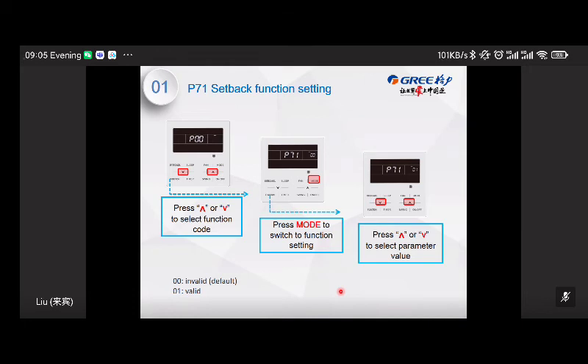So we developed a setback function. If you enable the setback function, when the customers go out, the units will run automatically. For example, in summer, if the room temperature rises above the setback limit temperature setting, the units will start automatically to make sure the room temperature will not be very hot, or in winter not be very cold, right? You can just consider it as automatic running during the absence, especially for the hotel project. Okay, so that's the code introduction for the wire controller.